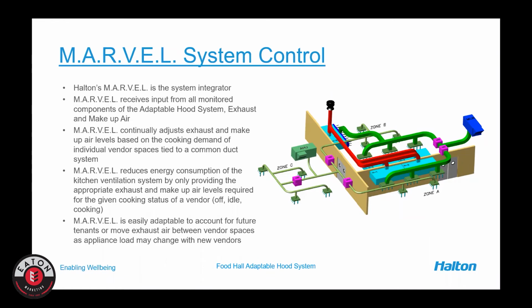This graphic shows that we have the ability to even zone those airflows based on the requirements of the space. This particular graphic shows 3 different zones, and we're tied into one exhaust and one supply system on those 3 zones, monitoring and sending that air where it needs to go. So it's a very flexible system, once again, that allows us to change over time as those vendor components change.